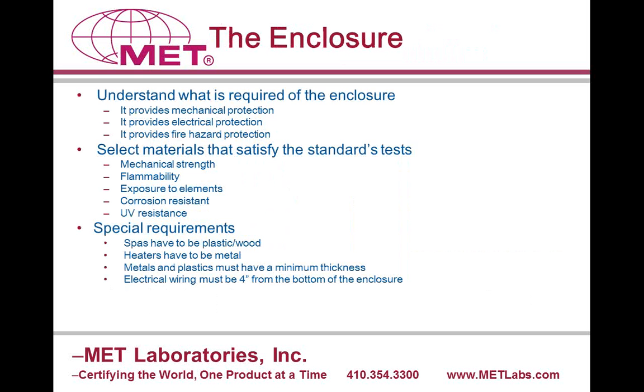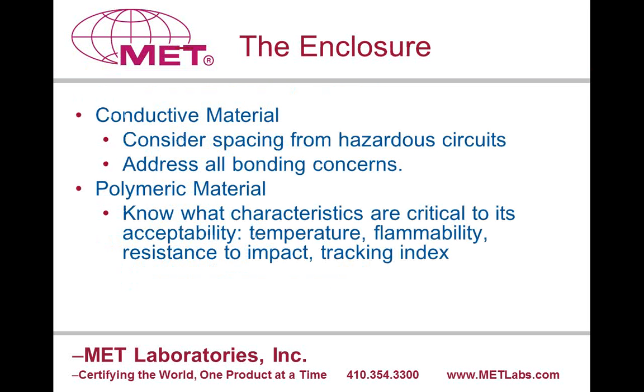Now, I want to spend a minute talking about the enclosure of an electrical product because it provides mechanical, electrical, and fire protection for that product. It's very important that you select the material carefully and select a specific thickness so that it can stand impact, not corrode, not catch fire. There are also some special requirements for water-related electrical products. For example, spas cannot be metal, heaters must be metal, cast and sheet metal have minimum thicknesses according to each standard, and plastics have minimum thicknesses to prevent them from catching fire.